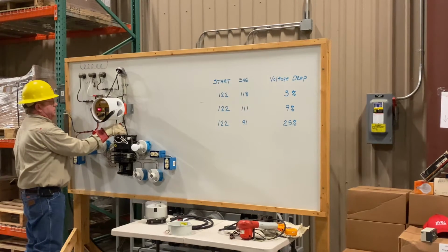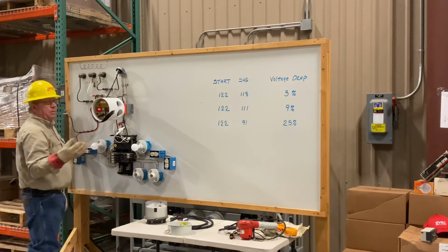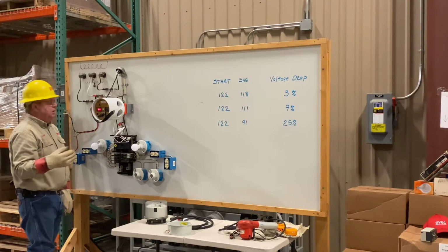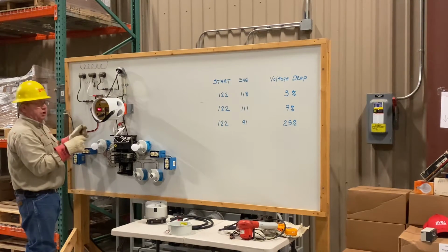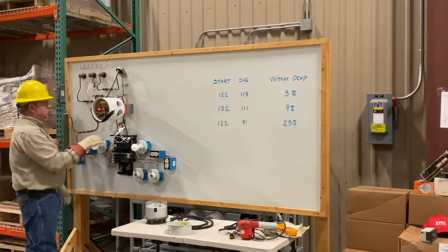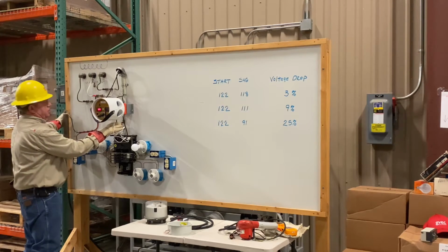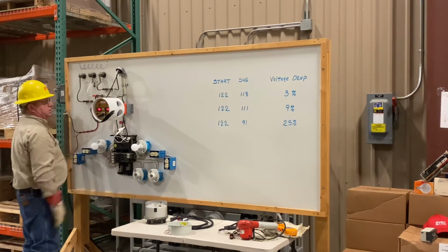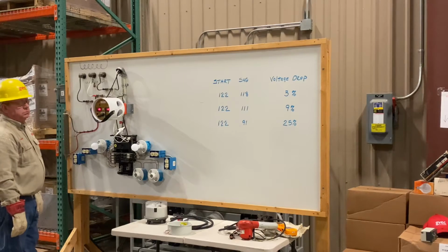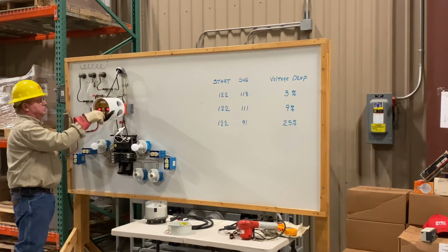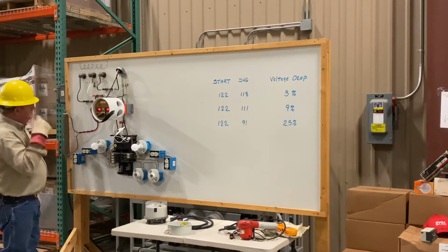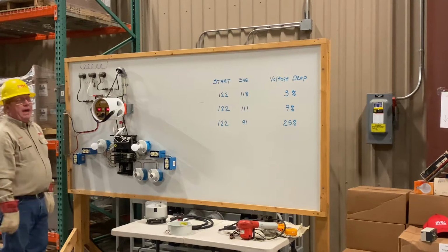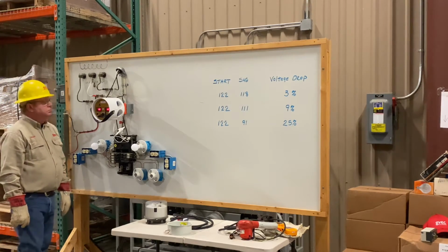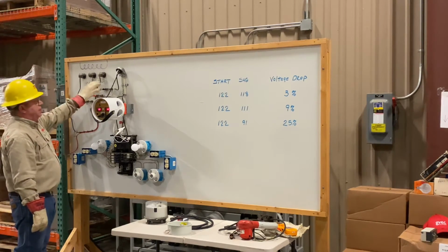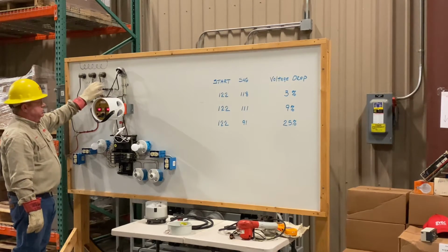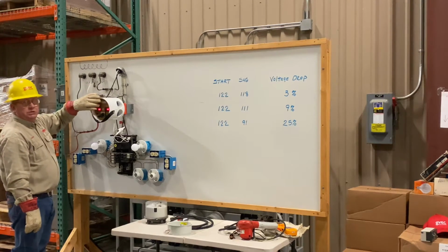I'm going to close this neutral connection, either with a bypass jumper that I made, some way my voltmeter is going to show me the total. I'm going to close this and restore the neutral. Now let's say we have a bad pin terminal. And what I'm going to do is I'm going to open up a hot leg. We have good balanced voltages.